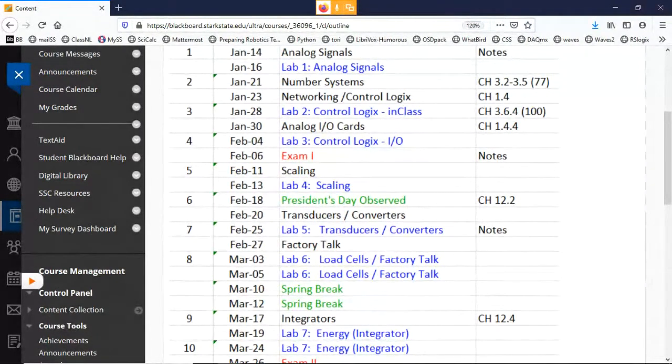What you really care about is that I've got a binary number inside of my PLC that represents how many milliamps are coming through, which really represents how many pounds are currently on the scale. So you can just scale that binary number to the actual weight on the load cell or whatever.